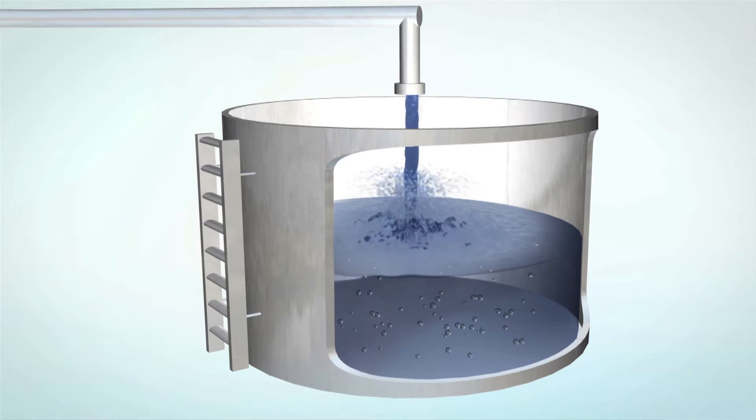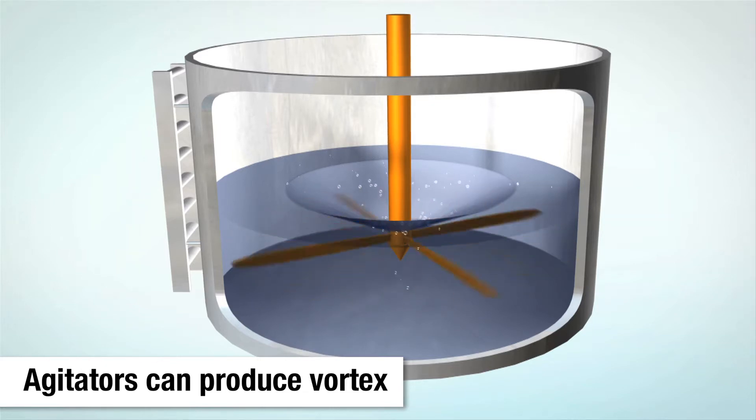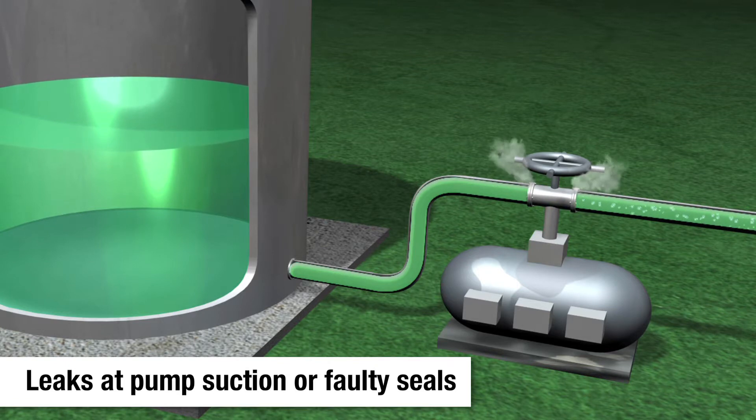Slug flow can occur as a result of long drops into tanks, where splashing occurs when the stream enters the liquid. The farther the liquid falls, the more air is entrained. Agitators can produce a vortex that entrains air into a liquid, especially when tank levels are low. Leaks on the suction side of pumps or in the pump seals themselves can also introduce air into a pipeline.